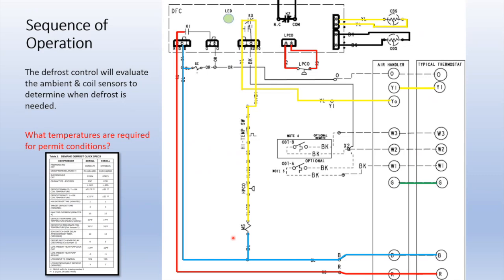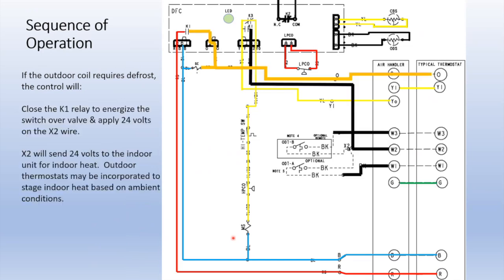Now we're in the normal heating mode of operation, so we're potentially developing frost, and when it's time to enter a defrost, now you're going to see the K1 relay on the board close, which will energize the reversing valve, putting the refrigerant in the opposite flow of direction. So now the outdoor coil is warm and the indoor coil is cold, absorbing heat in that indoor coil and putting it into the outdoor unit.